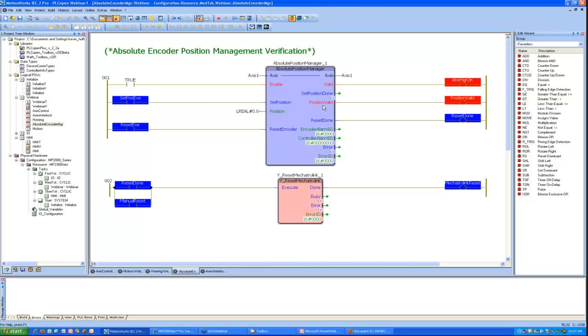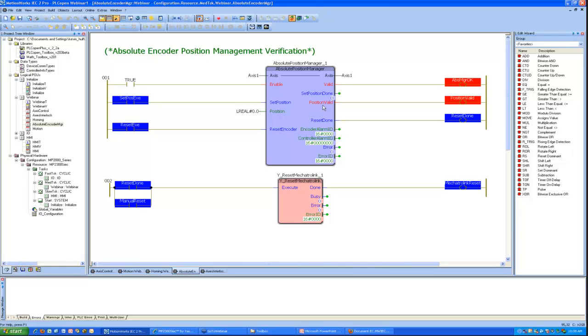So there's actually a retain output used in this case. So even after power cycle, this block can show that the position is valid. And it remains valid until there's any kind of encoder alarm related to the absolute encoder. So that's its key point of operation, is any time there's an encoder related alarm, it does a reset coil on its position valid output. And it will stay off until the alarm is cleared and until the set position input is executed.